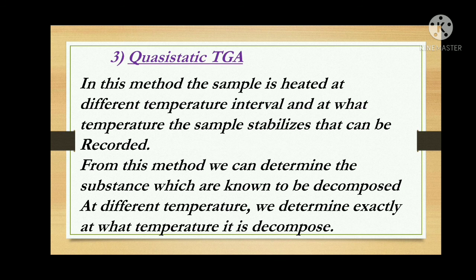The third type is quasi-static TGA. In this method, the sample is heated at different rates or different intervals of temperature, and at what temperature the sample stabilizes can be observed. We apply temperature at different intervals and record where there is no increase or decrease in weight. From this method we can determine substances which decompose at different temperatures — if we have a sample that can decompose but we don't know at exactly what temperature, this method helps us determine the exact decomposition temperature.